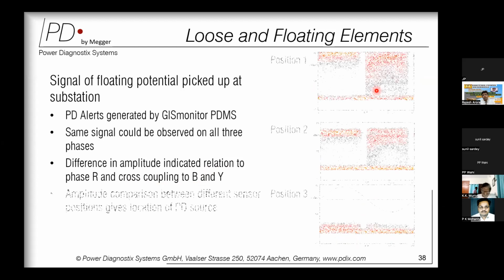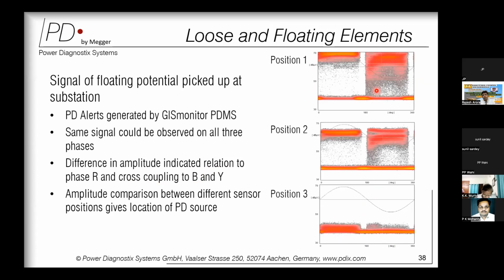We move forward, and if we have the same measurement done in parallel on those sensors as well, then we can compare the position on R phase of sensor number 1, sensor number 2 and sensor number 3, and we can say yes, 2 and 3 are capturing less amplitude of signal but similar nature, and point number 1 is capturing a higher amplitude. So on R phase, sensor number 1 is typically expected to have the partial discharge in its vicinity, closer to position number 1. So we've seen that a 6-channel or typically a 9-channel measurement really helps you zero down to the source of PD in one shot, and that is important. If you do the same thing channel by channel, then you will not have this correlation and you will be practically left blank in terms of your measurement and solution.